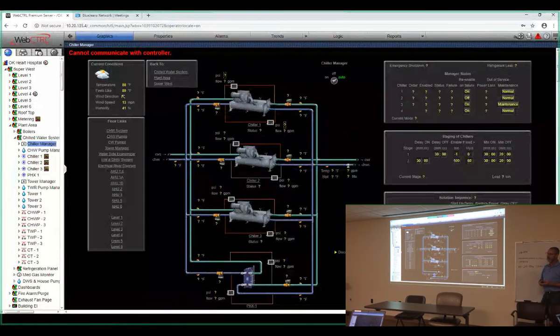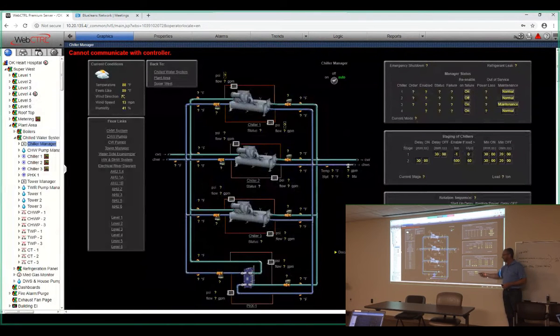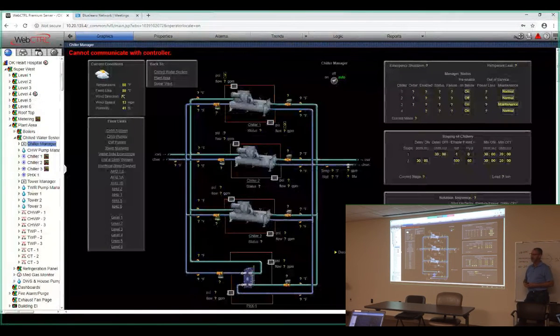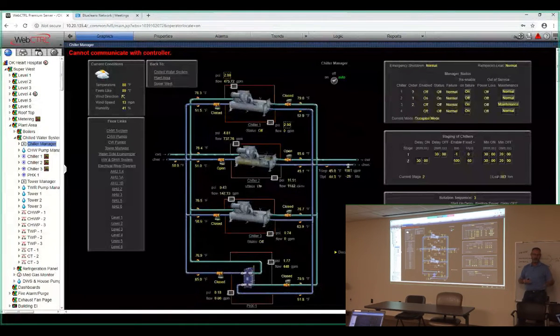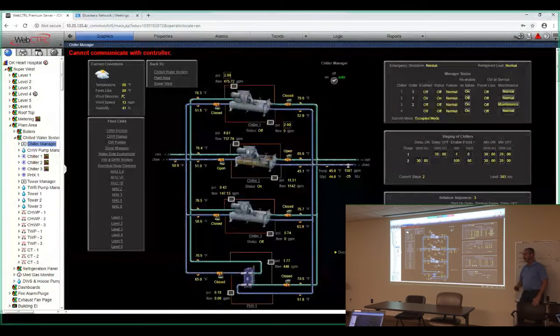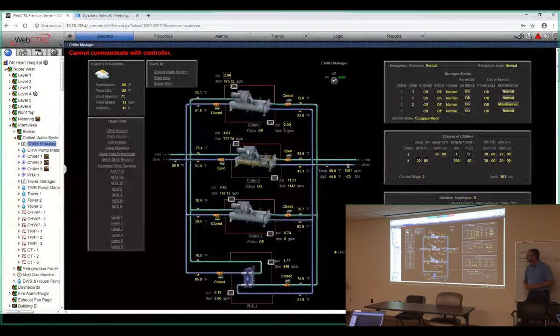Same thing with daily. Daily's going to rotate every day, but it's still going to rotate at a given time in the day, 1 o'clock, whatever you set in the system. Monthly, you choose the day of the month to rotate it, and the time of the day to rotate it. And that lets you know if you want to do it in the middle of the night or in the middle of the day, whenever you have the staff to make sure that they can watch that. So it just gives you a time so that you can sit down and say, okay, if we get rotated, everything's up and running, everything's good. So go ahead and put it back to manual.